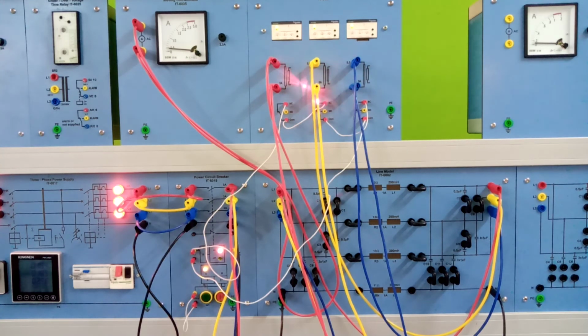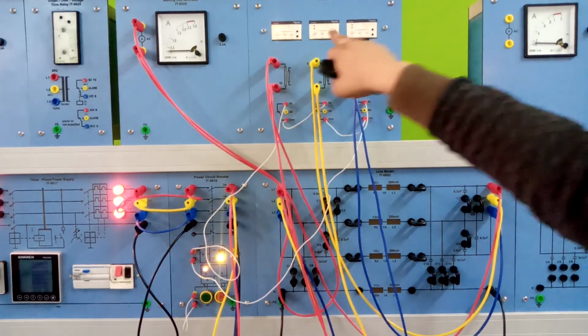Okay, so again I will demonstrate a fault on two phases. This time I will increase R1 and R3, the red and the blue, and let's see. Now these two phases are showing fault condition, but the third phase is already tripped. So if there is a fault on two phases, all the three relays have tripped. Again resetting them.